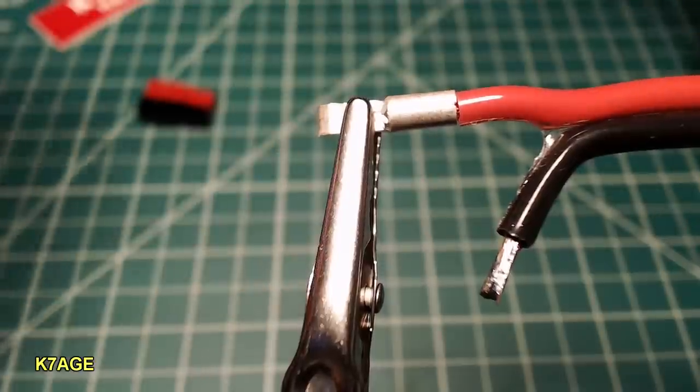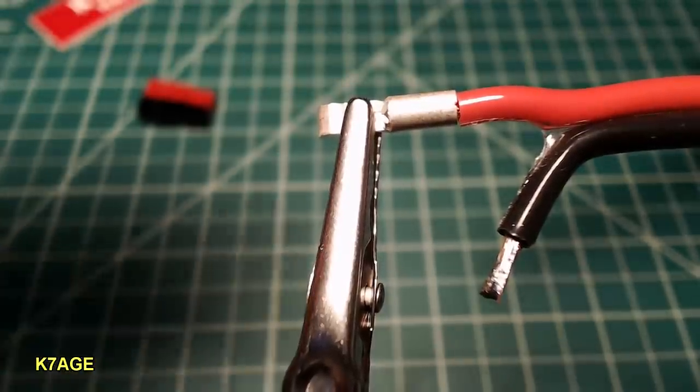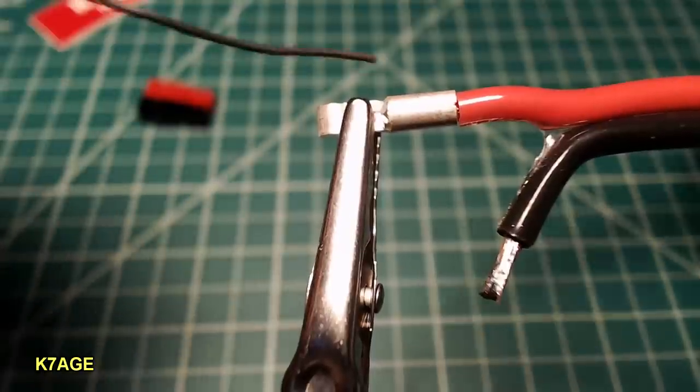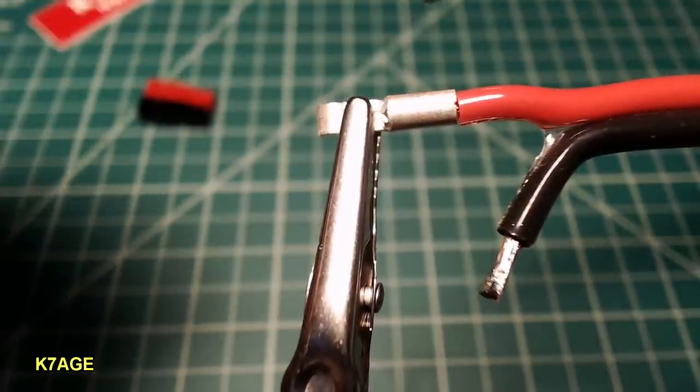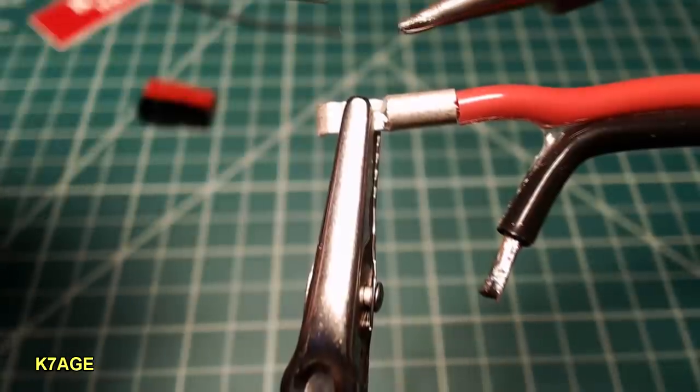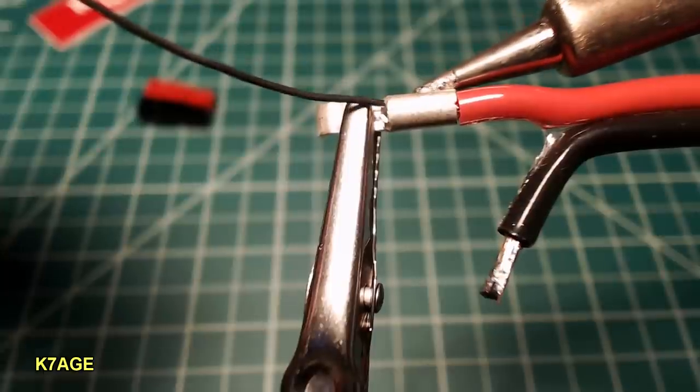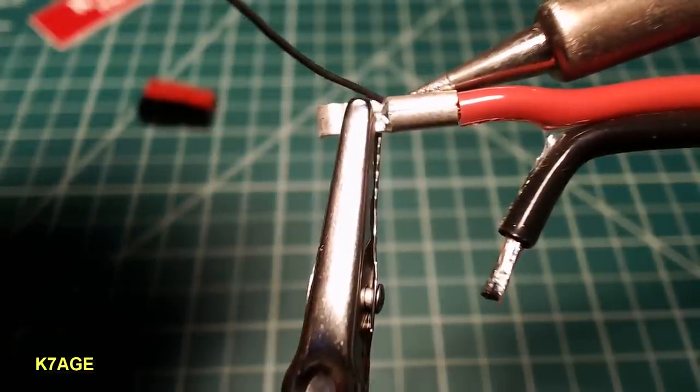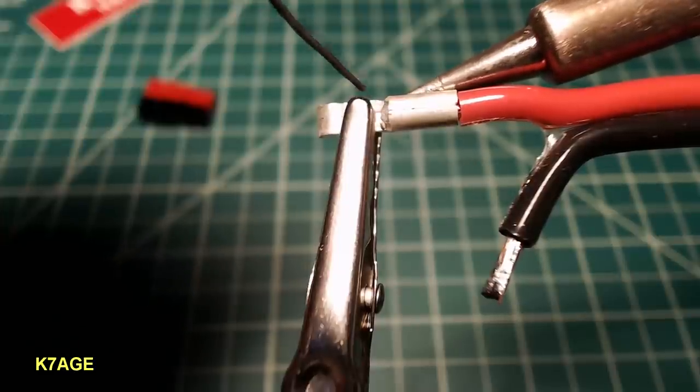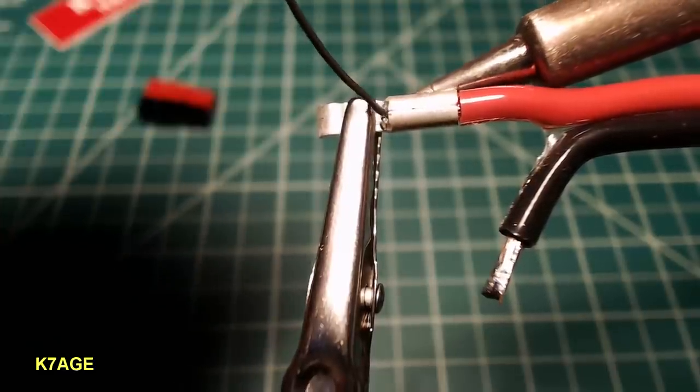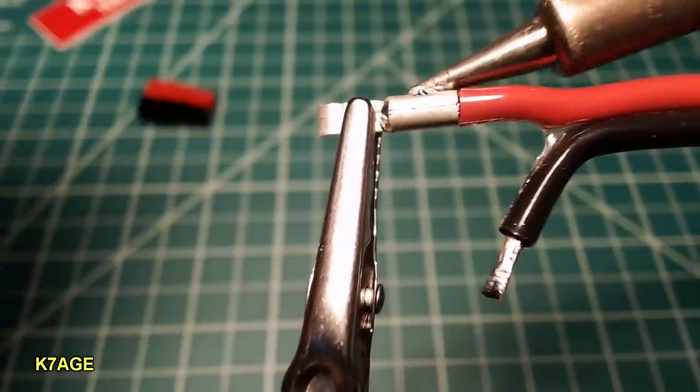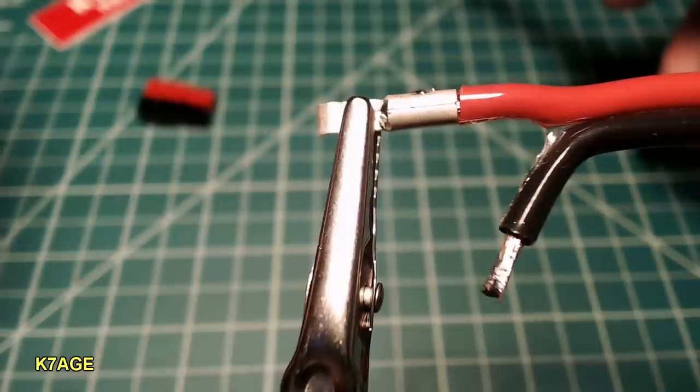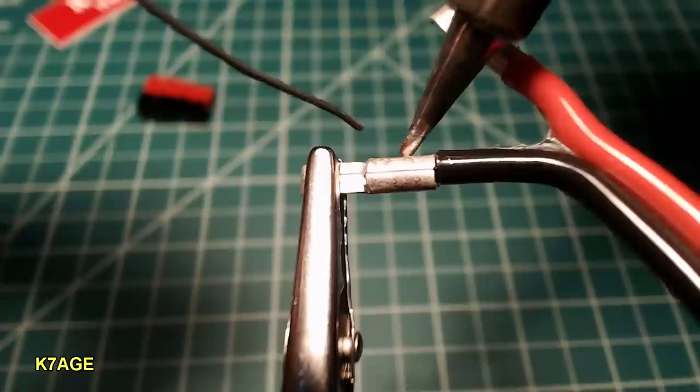Okay, I just flipped this over 180 degrees from what I just said to allow me to feed the solder in through the little opening here. So I'm just going to put just a tab on the iron here to help with the heat transfer. I want to keep the iron towards the wire end and feed it in from the pin end. And you do not want to get any solder on the contact area. So there it's flowing in and since it's tinned, I can see it going up the crack there and that should probably do. You also don't want to get a lot of solder on the outside of the pin otherwise it may not go into the connector body properly.